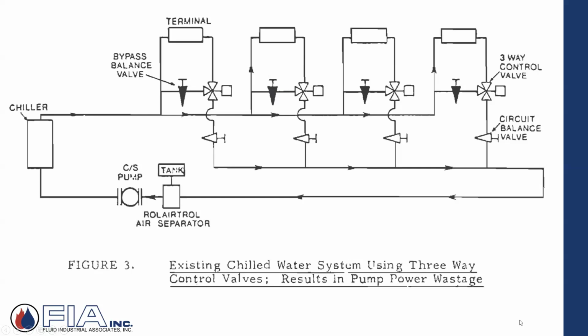Or the same pressure drop as the terminal unit. And what's going on here is, if this port right here, where this arrow is, was closed, so all the flow is going through the terminal unit, there's a certain pressure drop. We calculate, we figure it out. If the thermostat says, hey, close the 3-way valve, now this port's closed, the bypass is open. And I want to achieve that still kind of constant flow so the pump doesn't move up and down on this constant speed curve.